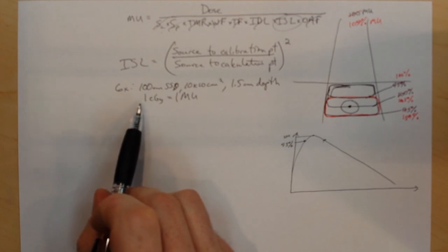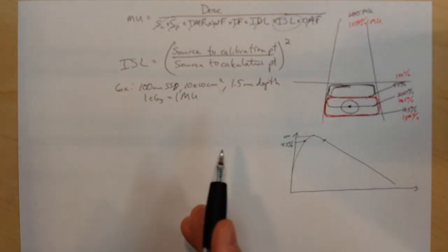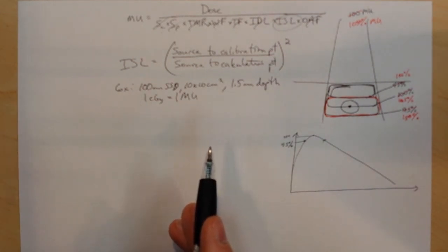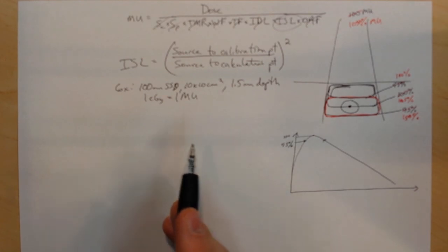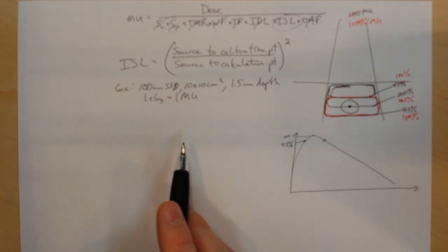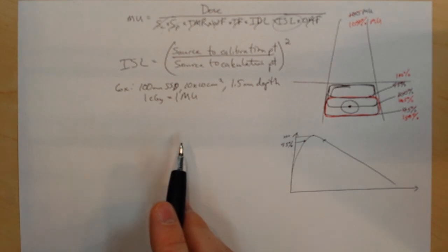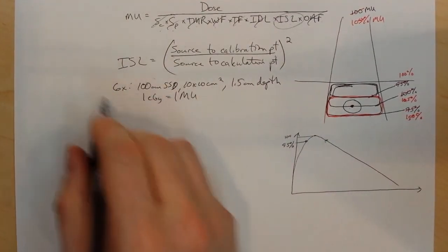And we do that because we want an isocentric technique. The gantries are mounted isocentrically, so they rotate 360 degrees around the patient. We don't want to have the gantry at a 0 angle and flip the patient upside down to do a PA field. We're way beyond that. But our calibration is calibrated at SSD. So how do we correct for that?